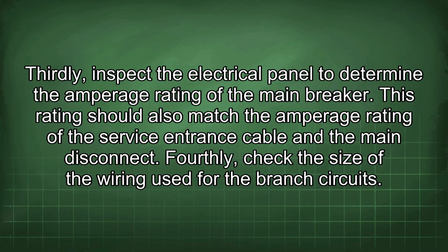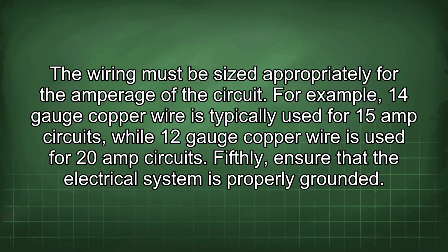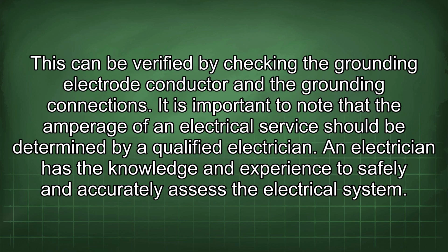Fourthly, check the size of the wiring used for the branch circuits. The wiring must be sized appropriately for the amperage of the circuit. For example, 14-gauge copper wire is typically used for 15-amp circuits, while 12-gauge copper wire is used for 20-amp circuits. Fifthly, ensure that the electrical system is properly grounded. This can be verified by checking the grounding electrode conductor and the grounding connections.